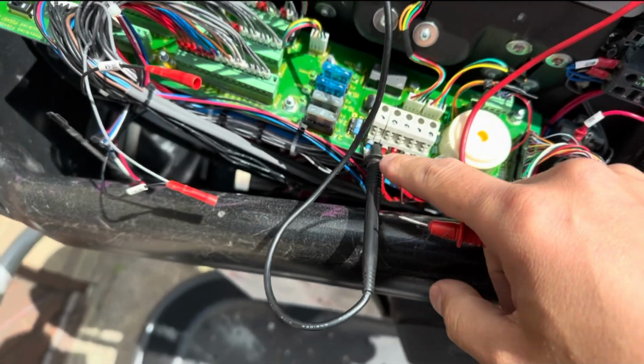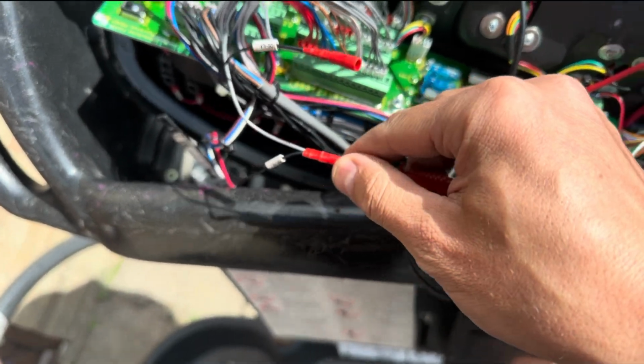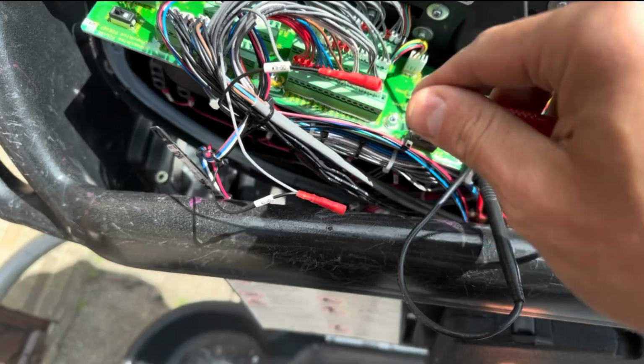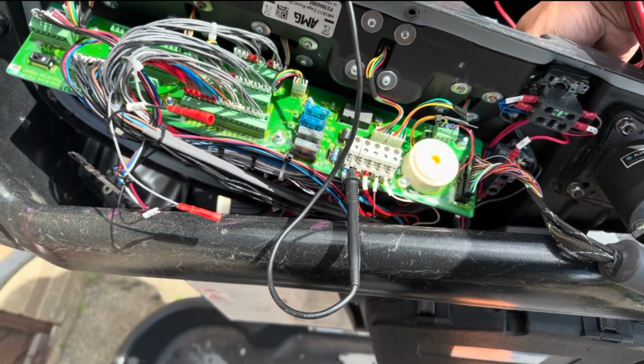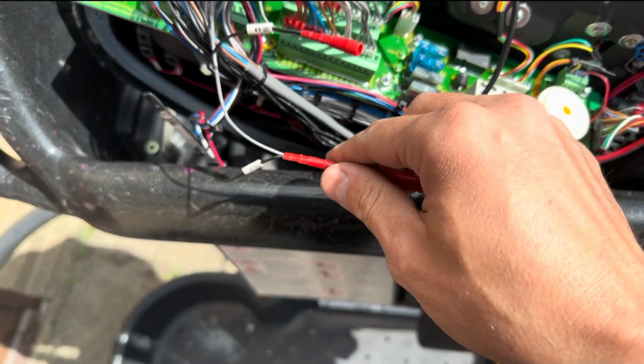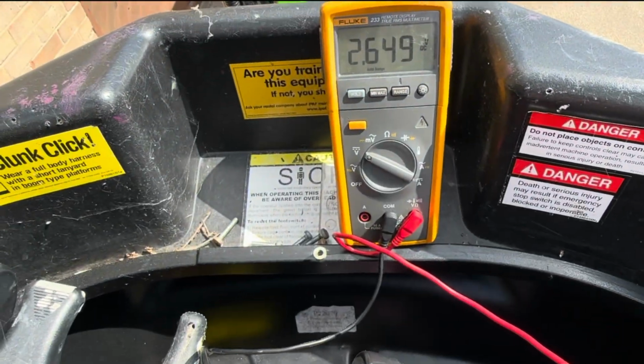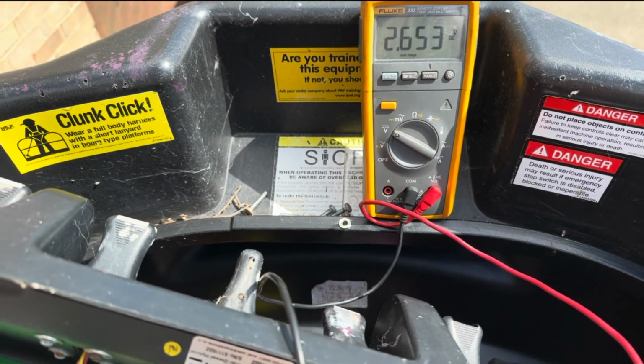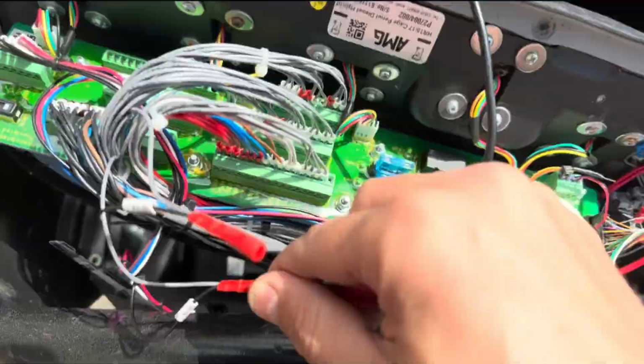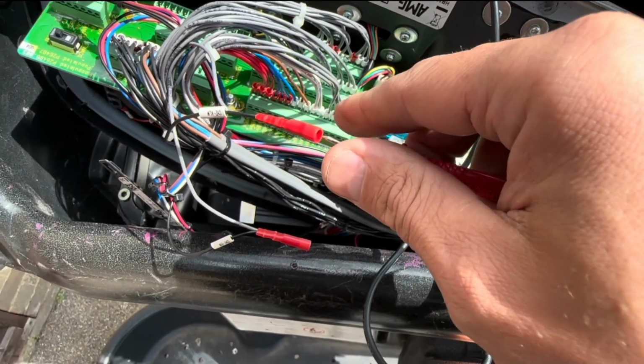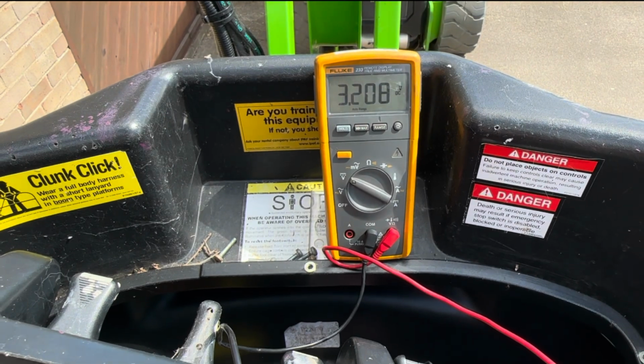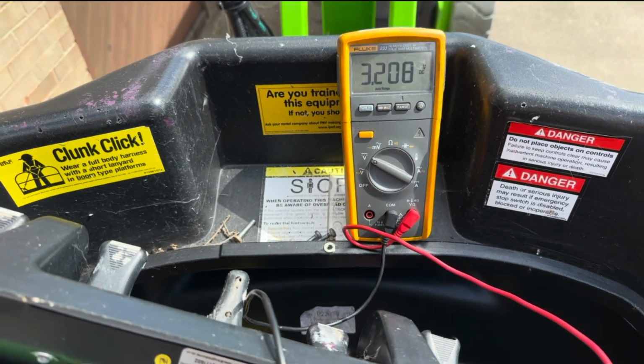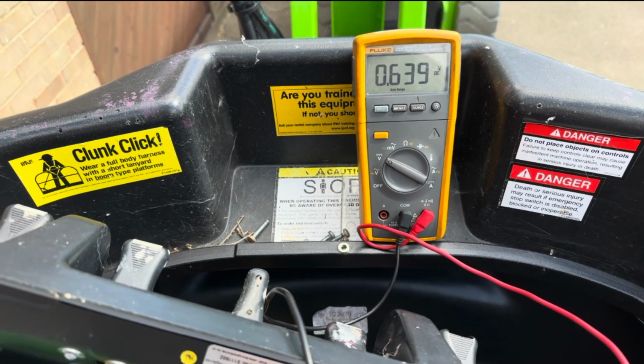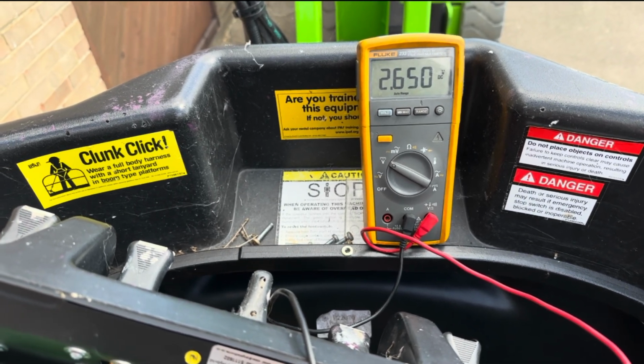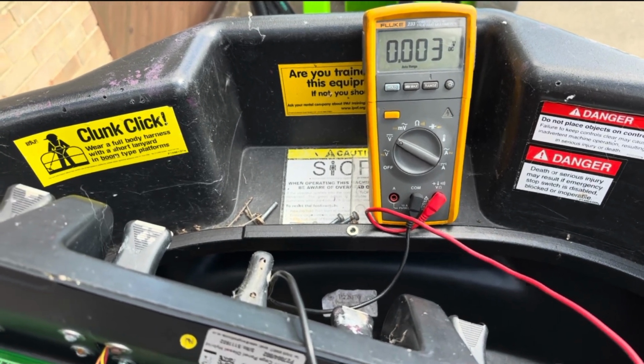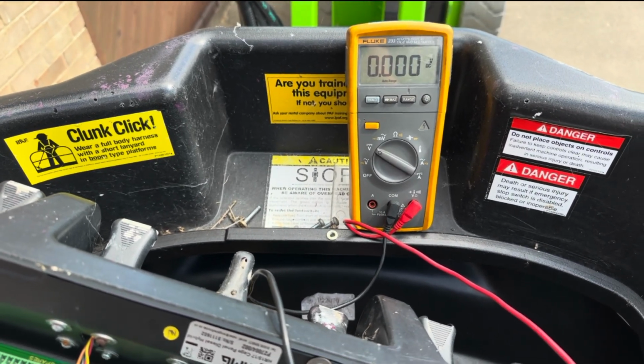Alright, so I've got my ground connection here, and I will measure the voltage on channel 1, channel 2 once the machine is started. So let's switch the machine on. The machine is on now, so that's reading 2.6 with me standing in it. The alarm is going off now, and channel 2 should be the same. So channel 2 is reading way higher, 3.2 for some reason. Okay, so 3.2, 2.6. So there's a big discrepancy in the channels. Okay, so I think that's where the problem is.